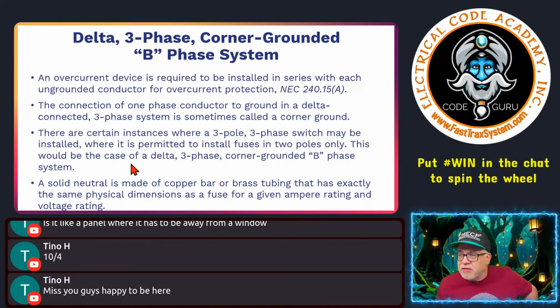I've only run into this in an industrial application where I had this situation on a corner-grounded delta system, and it was very specifically engineered for that application. Other than that, typically we're going to have fuses in all ungrounded conductors or circuit breakers in all ungrounded conductors to be able to break it and turn it off, okay? A solid neutral is made of copper bus or brass tubing that is exactly the same physical dimensions as a fuse for a given ampere rating or voltage rating, okay?